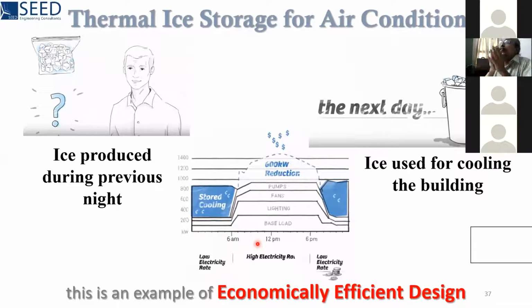All the offices are operational. By about 3 p.m. or 4 p.m., all the building material which has absorbed heat from the sun will start giving it out. So at the peak load condition, you will feel that your room is very hot during 3 to 4 p.m. time. So these are the peak hours. During the peak hours, you need more chilled water to have an effective cooling. So if you draw power from the grid during that time, you will pay more.